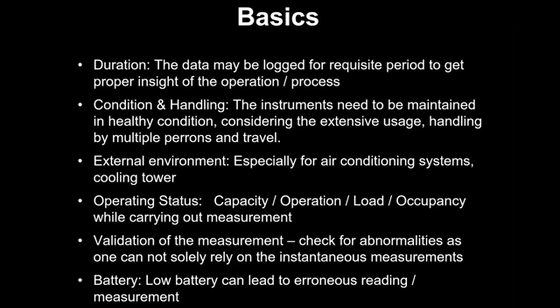Duration is the same way; earlier it was time, then we say duration. So if it is required to be logged, we log it. This logging also becomes critical for, say, textile and pharma industries, where they are trying to monitor temperature and humidity. There are temperature humidity loggers available which are not very expensive. We leave them inside, even in a data center, because measuring for a few minutes is not going to give you the correct value. So we place the data loggers at appropriate locations and capture data for 24 hours at maybe 1 minute or 5 minute intervals, to see the variation or profiling.